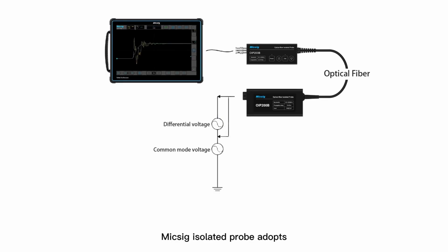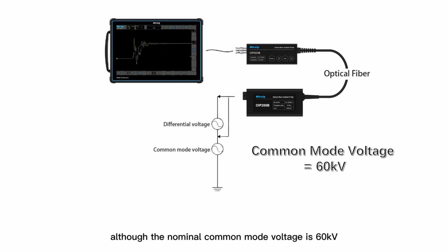The Micsig isolated probe adopts fiber optic isolation technology. It transmits the signal from end to end via a fiber cable, without electrical signal, achieving true electrical isolation. It is able to conduct floating measurement under high common mode voltage. Although the nominal common mode voltage is 60 kV, you don't actually have to worry much, as the optical fiber isolated probe can test any high voltage as long as the environment allows.